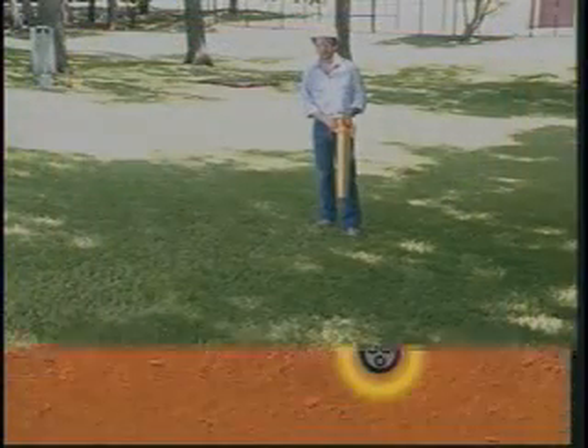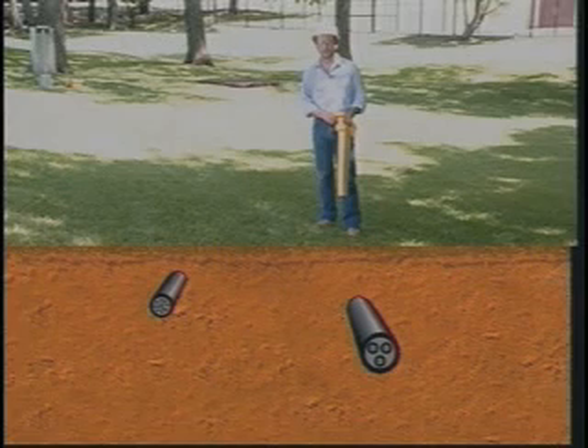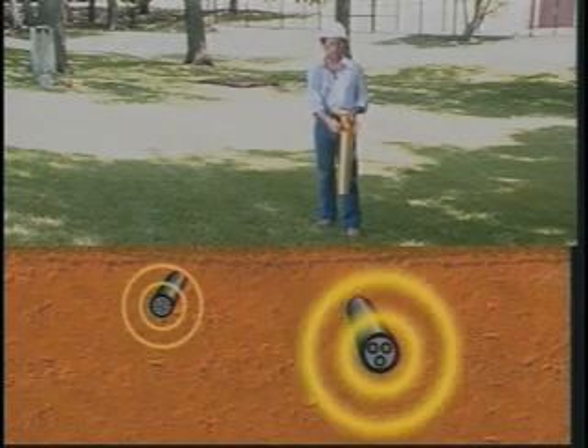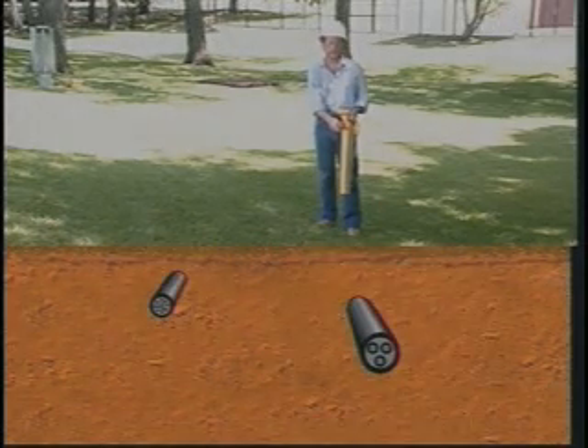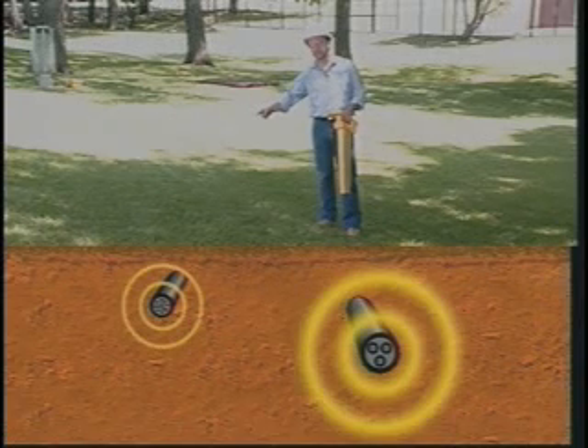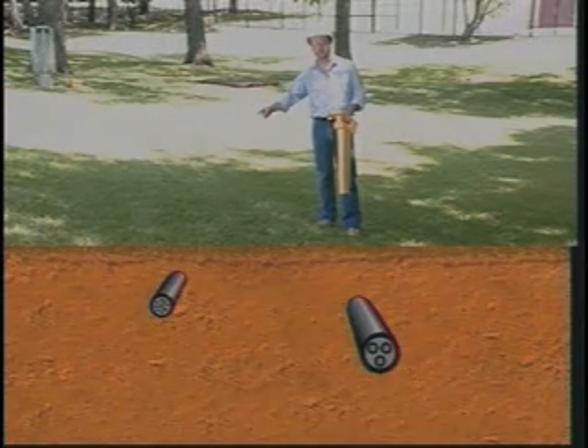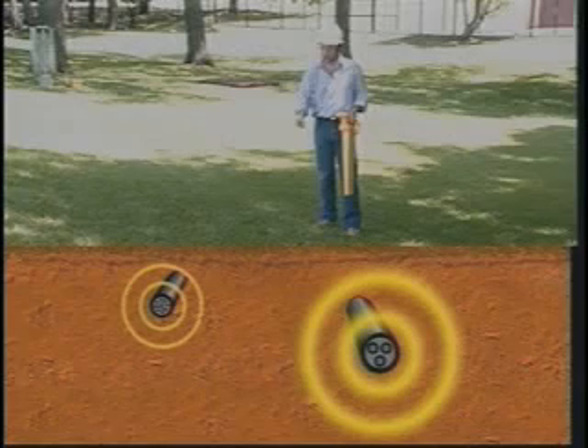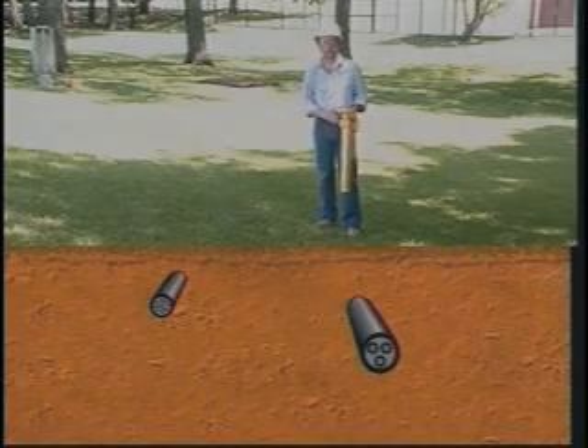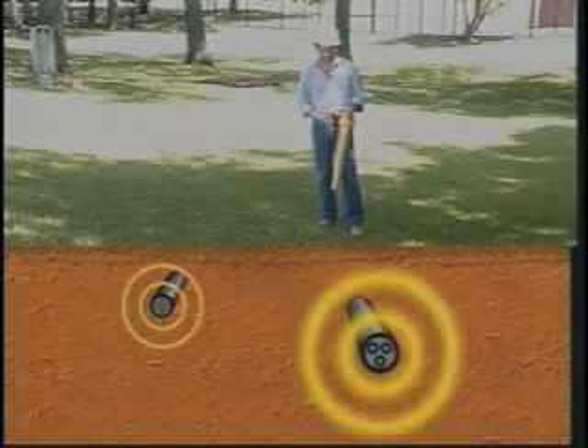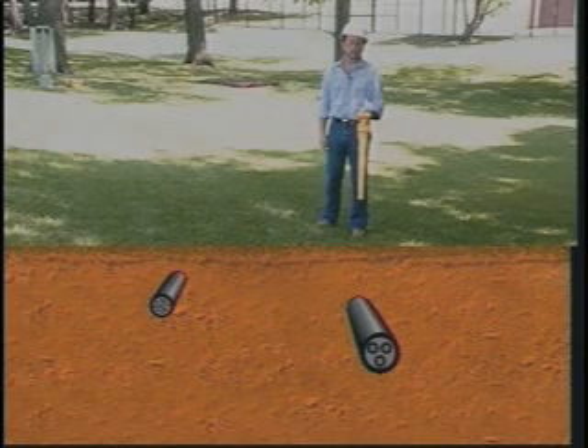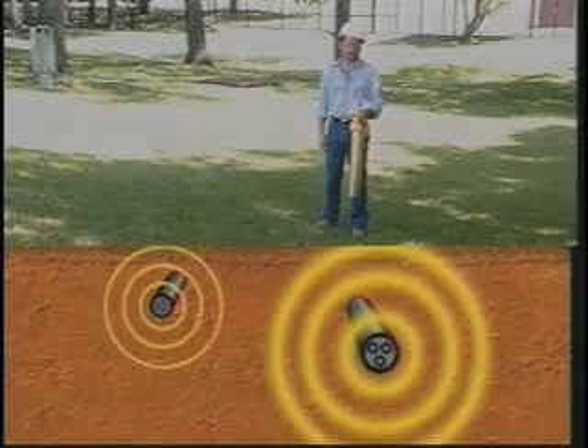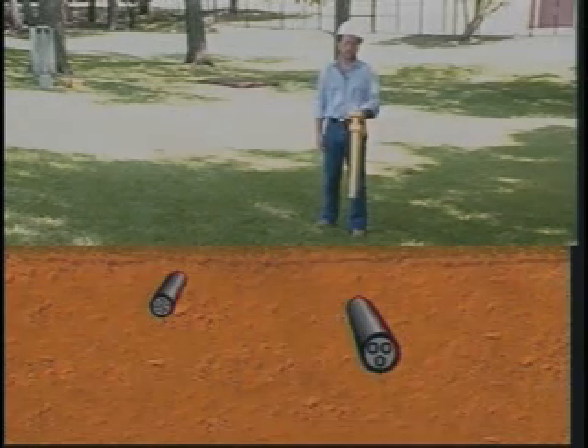The current mode is useful for verifying that you're tracing the correct cable. Here, the transmitter signal was applied to the deeper cable. The other cable is carrying a weaker signal because of common grounding. This looks like two trace paths, so which is the correct one? Since the cable with the highest current is most likely the target cable, you have to check each response in the current mode.